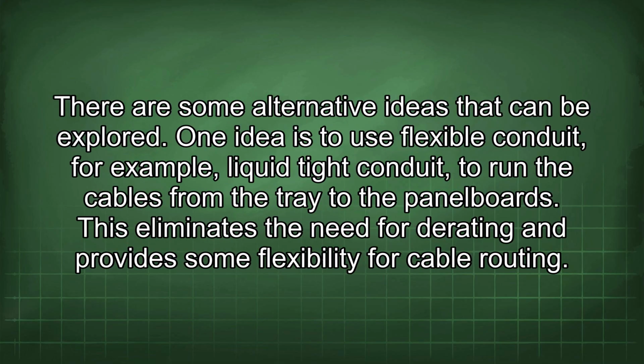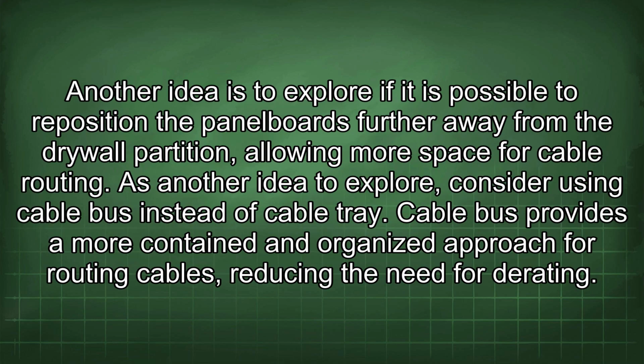There are some alternative ideas that can be explored. One idea is to use flexible conduit, for example, liquid-tight conduit, to run the cables from the tray to the panel boards. This eliminates the need for derating and provides some flexibility for cable routing. Another idea is to explore if it is possible to reposition the panel boards further away from the drywall partition, allowing more space for cable routing.